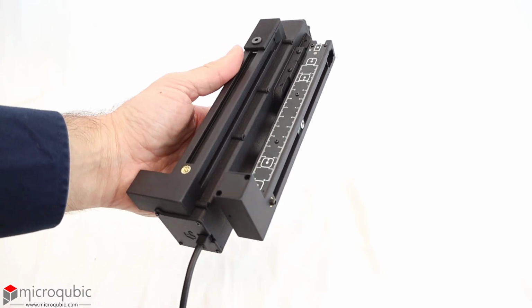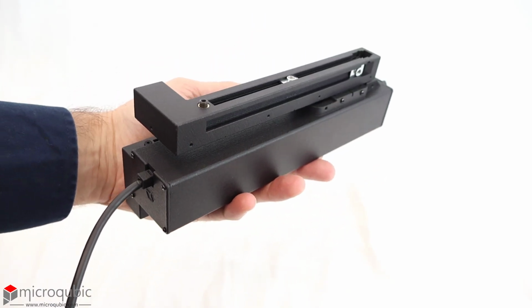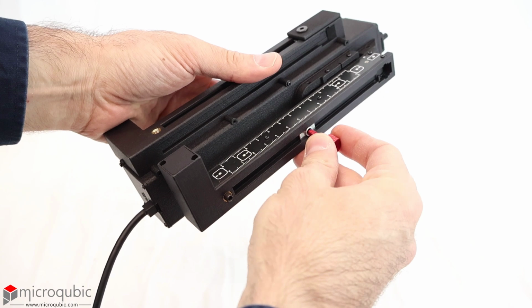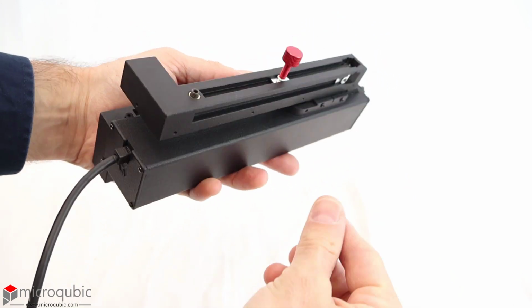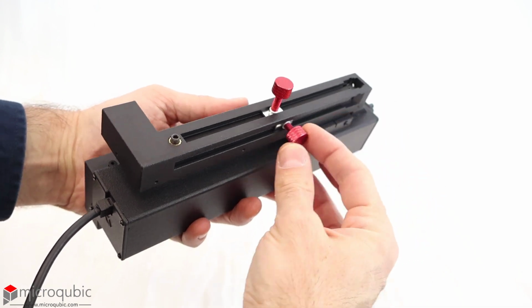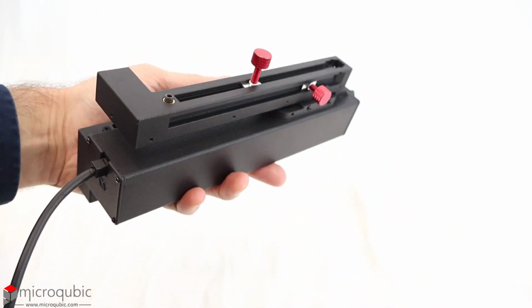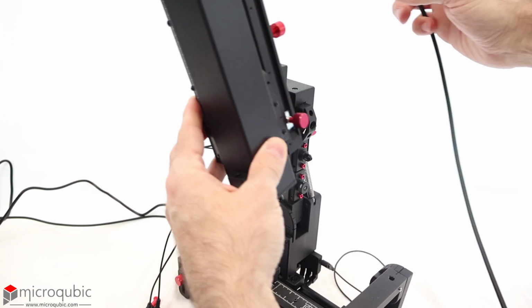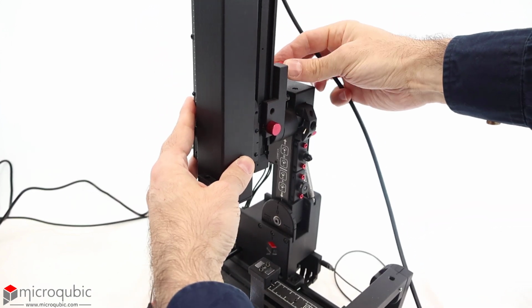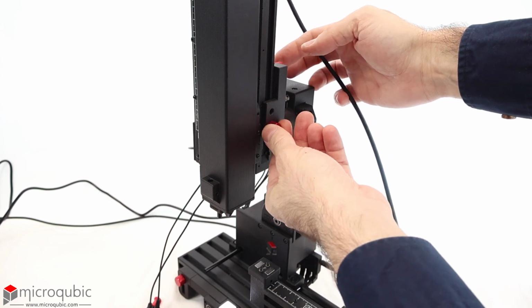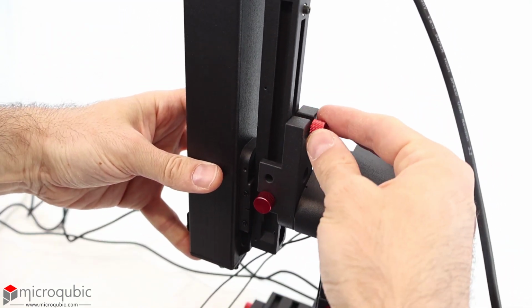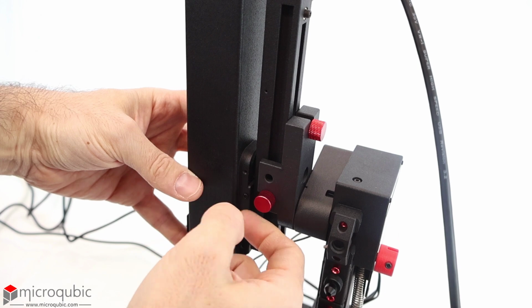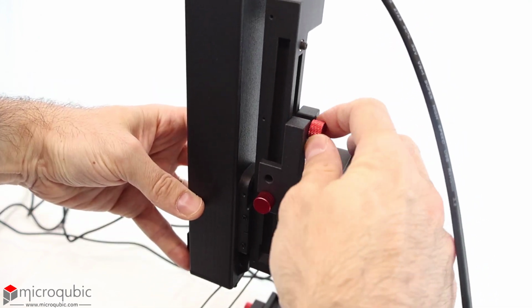The next step is connecting the camera unit to the tilting module using 2 thumb screws. Insert the longer screw to the bottom of the module and the shorter one to the side. These screws should easily slide along the channels. Fix the camera module to the tilting arm. You can adjust its position manually depending on the imaging mode and the sample type, and then use motorized actuators for precise focus and zoom adjustments.